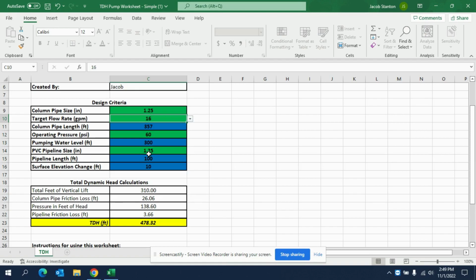Now, larger applications, if we're talking pumping hundreds of gallons a minute and we have maybe quite a few 90 degree elbows or check valves or flow meters, then yes, I probably would go in and use a friction loss chart for fittings and factor those in some form or fashion to my total dynamic head calculations. But in general, for most residential and even light irrigation, agricultural uses, as long as your pipe is sized properly, the additional head pressure from elbows and fittings and things like that is negligible. So I usually don't worry about it. I don't get too far into the weeds on those things.